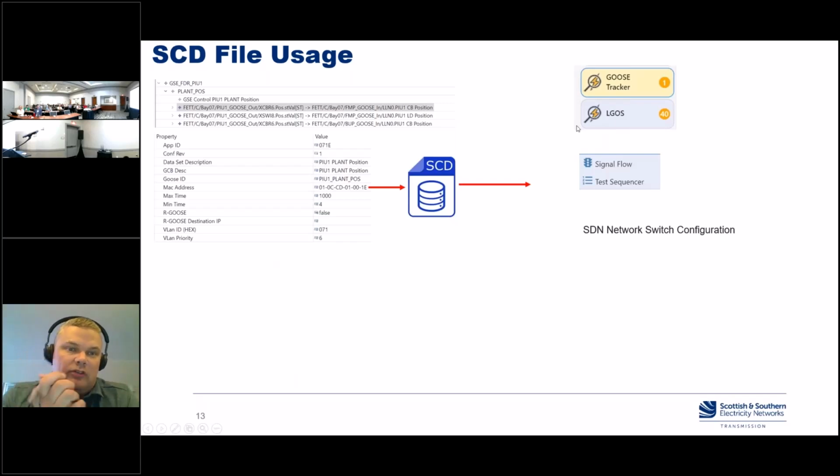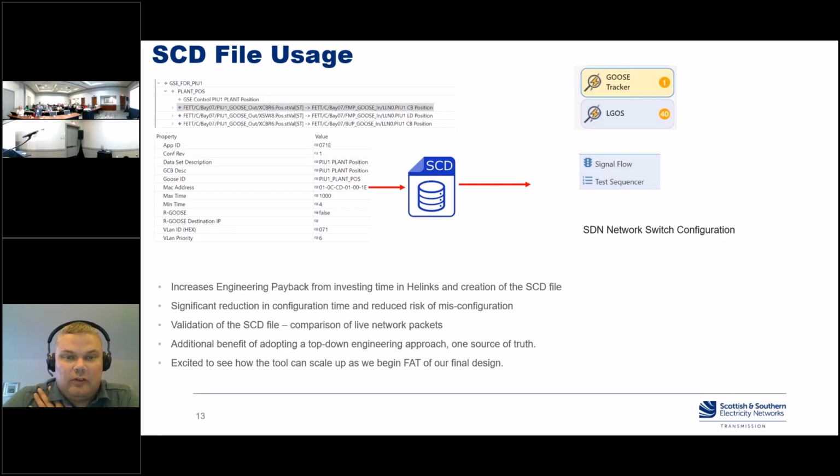And yeah, finally, just a word on SCD file usage. I think one of the key things that I've seen in the last 10 years is how the SCD files become more central to applications and diagnostics. Obviously, the SCD file is your key. It's good to see applications consuming that and being able to create test sets or test applications or test sequences from that directly with minimal user interface. It's really time saving. It gives you confidence that everything that's in the SCD is configured.